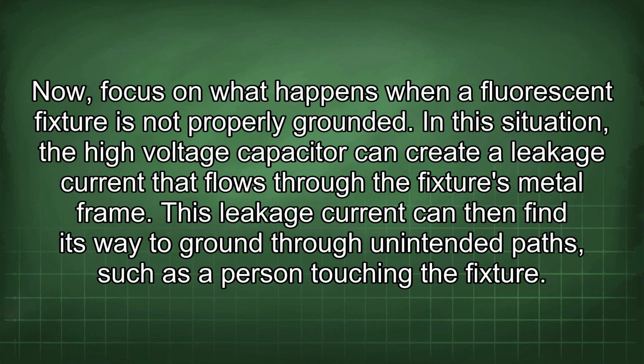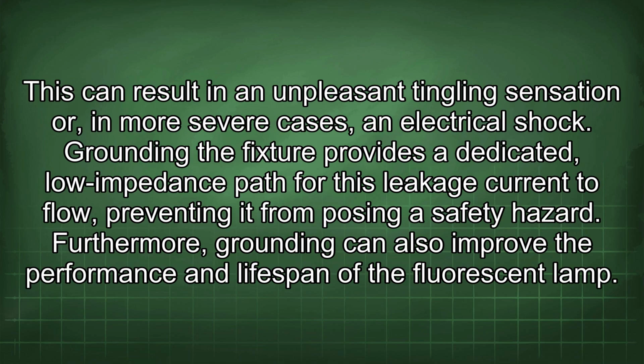Now focus on what happens when a fluorescent fixture is not properly grounded. In this situation, the high voltage capacitor can create a leakage current that flows through the fixture's metal frame. This leakage current can then find its way to ground through unintended paths, such as a person touching the fixture. This can result in an unpleasant tingling sensation or, in more severe cases, an electrical shock. Grounding the fixture provides a dedicated, low-impedance path for this leakage current to flow, preventing it from posing a safety hazard.